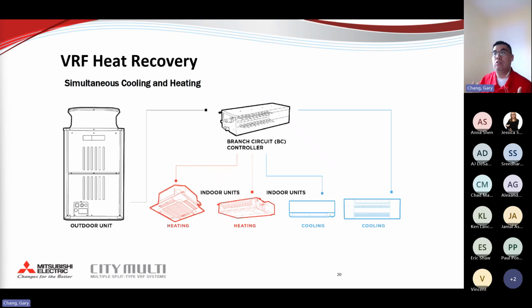And on top of that, we're using a VRF system. You can see just small refrigerant piping going into what we call a branch box. And then the branch box will be able to provide heating and cooling at the same time. So for example, if I'm in the office, instead of June 26th, let's imagine this is October 15th. I need cooling and some of you want heating. Therefore, the unit itself can have heating and cooling at the same time to meet your demand. So that's also increasing comfort in many cases. And the more you use it, actually, the more efficient the system is.